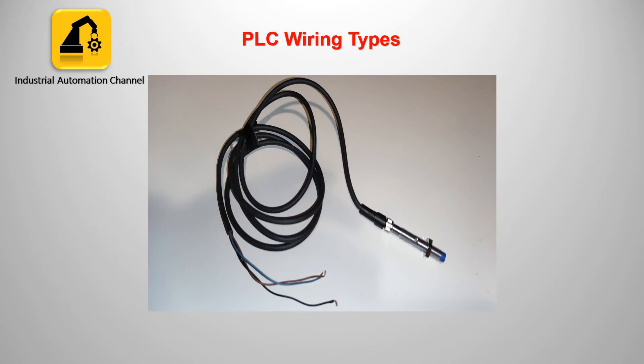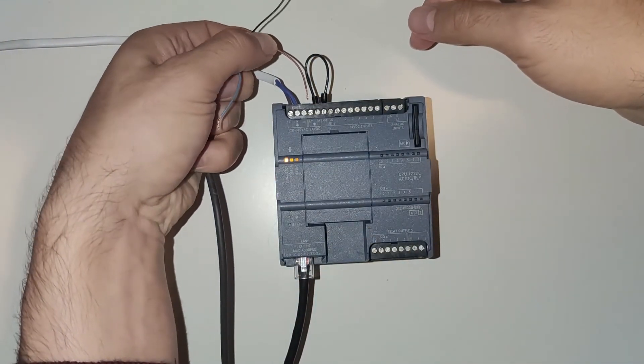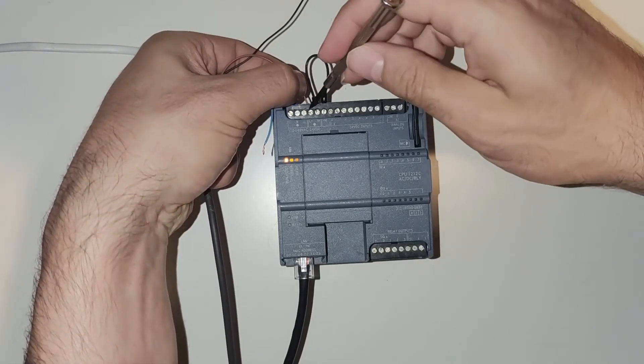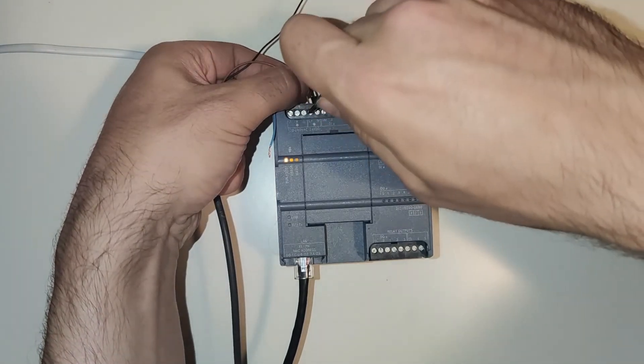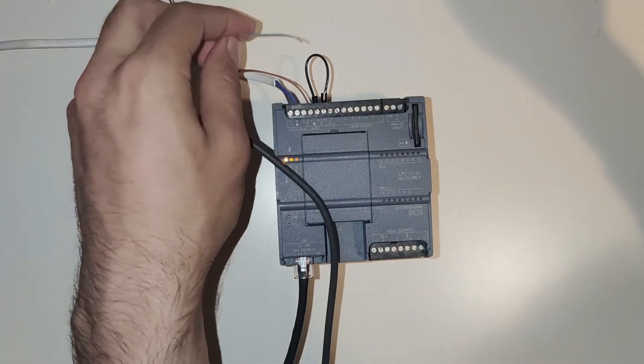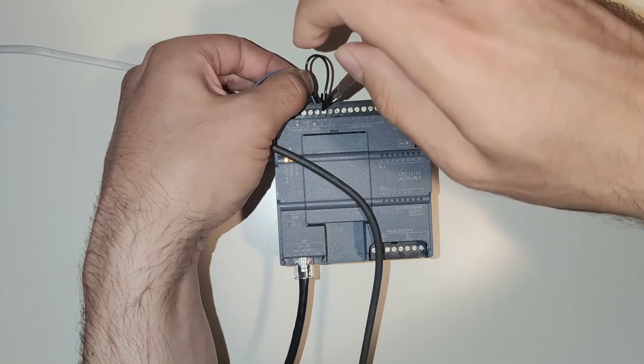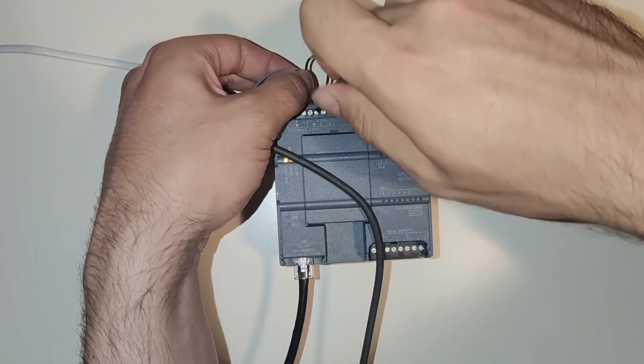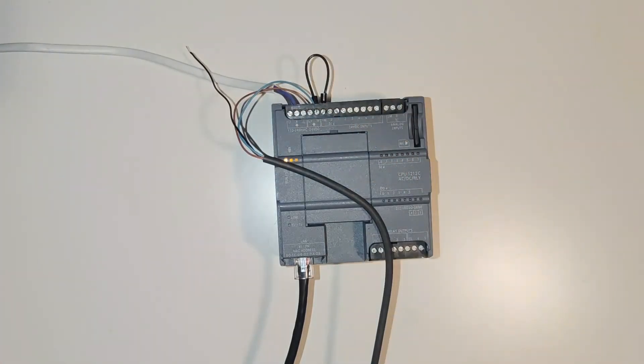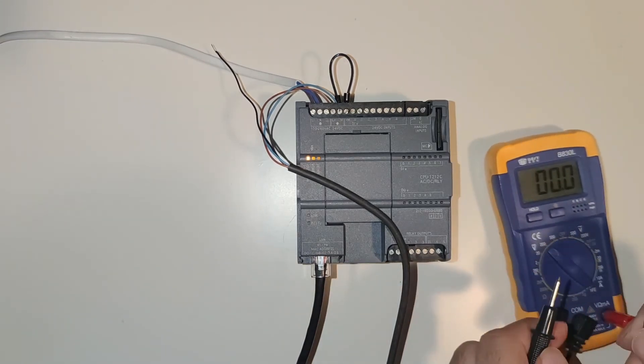Let's show this in TIA Portal and with the PLC. I have a PNP sensor and I will show you how to connect it to the PLC and wire it. You need to connect the brown wire to L plus, then the blue wire to M. If you test the sensor with a multimeter, it will give you 24V when the sensor detects an object.